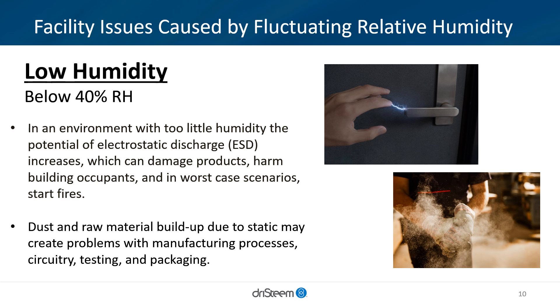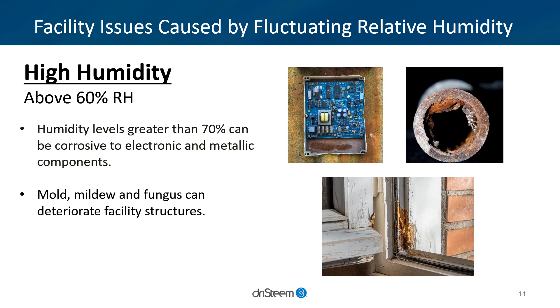Dust attracted by static electricity may cause problems with manufacturing processes, circuitry, testing, and packaging. RH higher than 70% can be corrosive to electronic and metallic components. In some environments, exceeding 60% RH can increase mold, mildew, and fungus growth, which can deteriorate facility integrity.